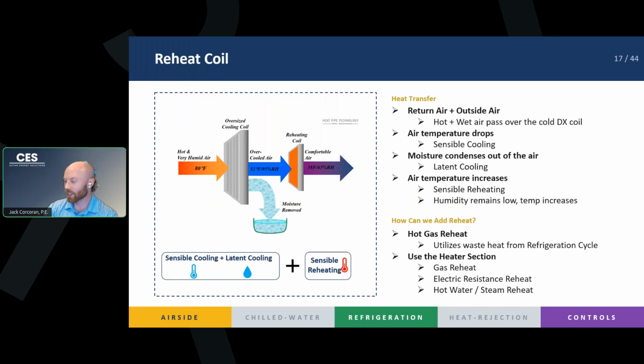You're gonna get condensation on ducts. You're gonna get maybe condensation on surfaces in the room. But you can have a reheat coil section, right? We overcool our air, wring out the moisture, and then we reheat it back up to whatever temperature we need, right? So if the space is cold but damp, we can reheat it back. We can overcool to get rid of the moisture, and then we can reheat it back up with our reheat coil section in order to get our 70-degree room air temperature that's dry into the room, not a moist 70 degrees. So as we said, right, we have sensible cooling, latent cooling, and then we have sensible reheating. The humidity remains low, but the temperature increases to what we need for the space.